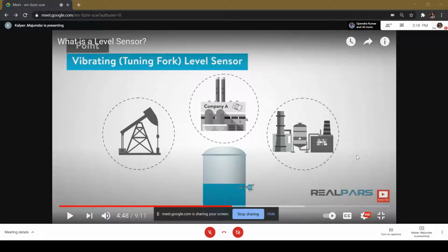In the context of a level switch, the very name says that it is a switch operated by liquid level. So how is the switch activated? By liquid level. When the liquid level rises to the position of the switch, the switch is activated and the state of the contact changes. So what is normal? When the input activation is not present, that is, when the liquid level does not exist at the position of the switch.